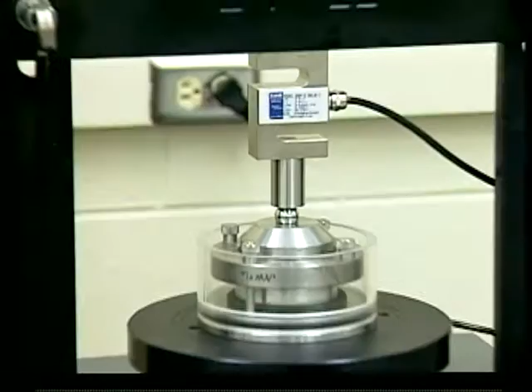All right, we're back to do our machine deformation. Something that was not recorded: we were checking the calibration, making sure that we're good to go. So what we did is we checked the load cell calibration and the displacement calibration. Those are very important because they're going to give us the correct results for the machine deformation, especially the load cell. So we took the load cell out of the frame, put it on the counter, and we put a known dead weight, which was about 17 pounds, and we checked it. It was about 17 pounds. So that looks good. We checked the calibration.